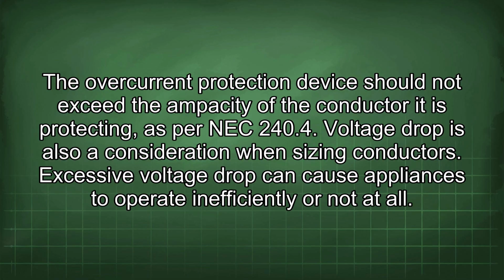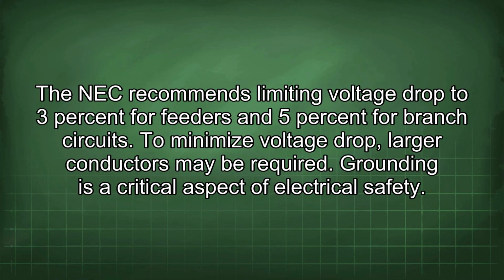Voltage drop is also a consideration when sizing conductors. Excessive voltage drop can cause appliances to operate inefficiently or not at all. The NEC recommends limiting voltage drop to 3% for feeders and 5% for branch circuits. To minimize voltage drop, larger conductors may be required. Grounding is a critical aspect of electrical safety.